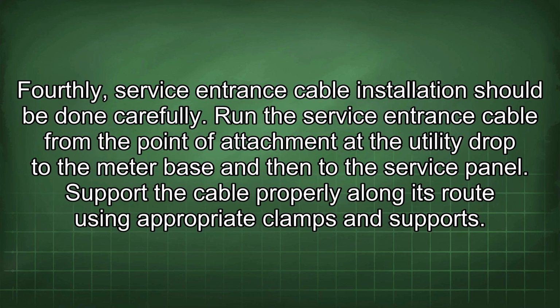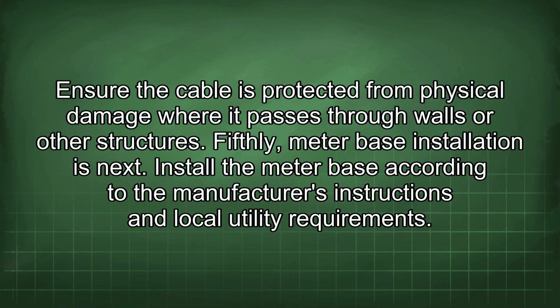Fourthly, service entrance cable installation should be done carefully. Run the service entrance cable from the point of attachment at the utility drop to the meter base and then to the service panel. Support the cable properly along its route using appropriate clamps and supports. Ensure the cable is protected from physical damage where it passes through walls or other structures.